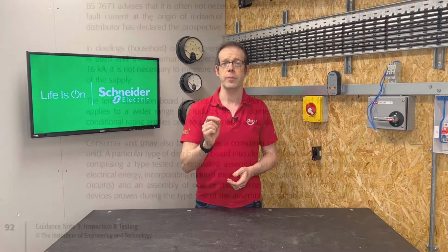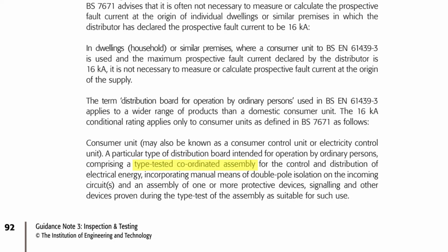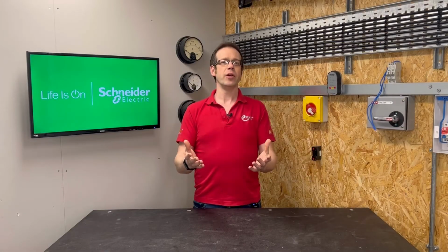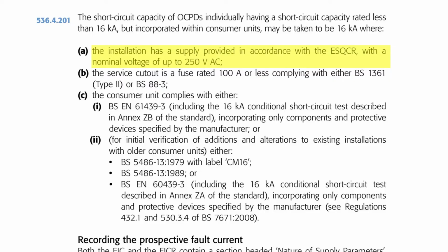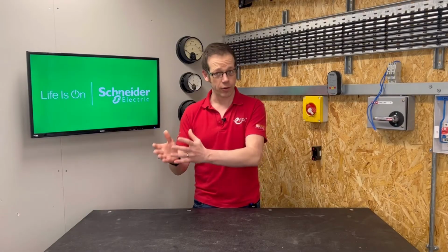us that as long as the consumer unit is a type-tested, coordinated assembly, so no mixing and matching of brands, with a double-pole main switch, meeting the requirements of BS 61439-3, our circuit breakers can be considered to be rated at 16 kA, which is suitable for our domestic installations as it matches the value quoted by our DNO. There are a few other criteria that must also be met regarding the supply, which are the incoming supply must be provided in accordance with the requirements of the Electricity Supply Quality and Continuity Regulations, with a nominal voltage below 250 volts and the cutout fuse is either a BS 1361 Type 2 or BS 88-3 rated at 100 amps or less. Obviously these are things we would ensure but are really the DNO's responsibility.